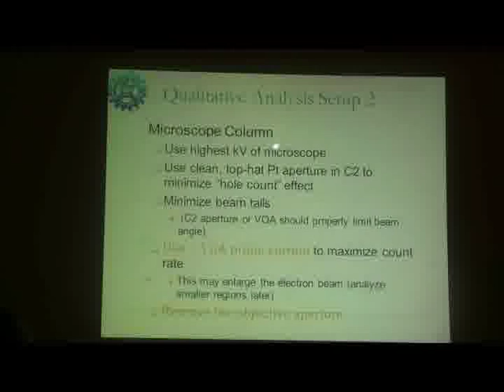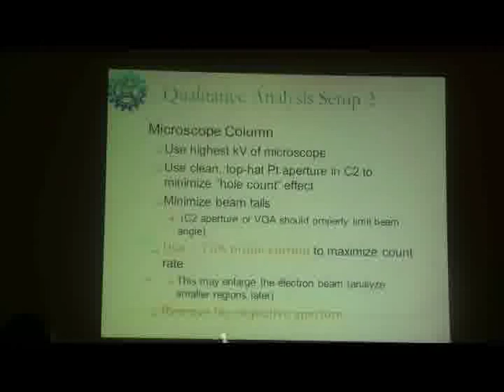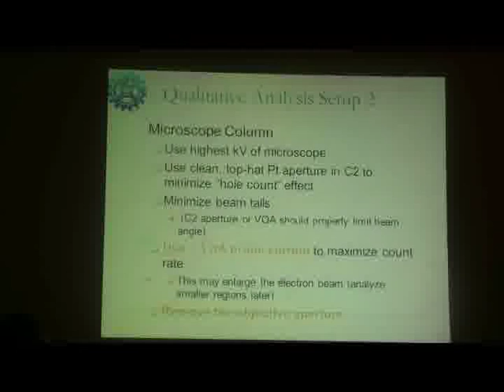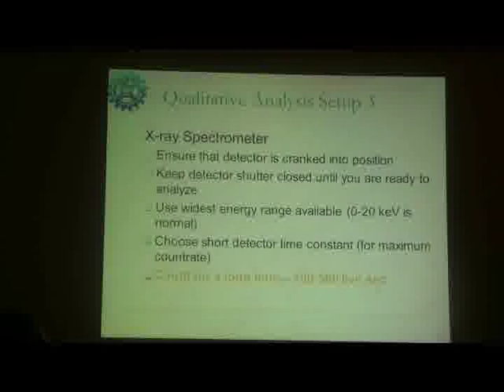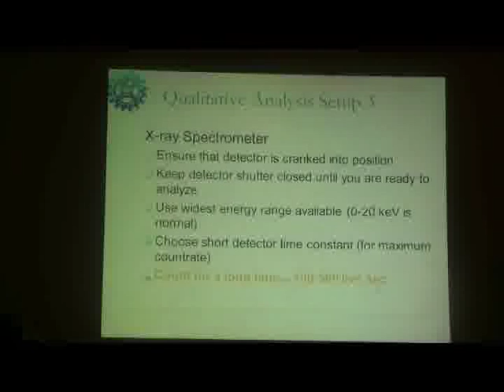So this is also with respect to the microscope. You have to have a large spot size. You have to use the highest kV possible. You should not use a lower kV for detecting higher energy elements. So you optimize the kV, and sometimes you have to remove the apertures also so that you get more beam and more current and more interaction with the specimen.